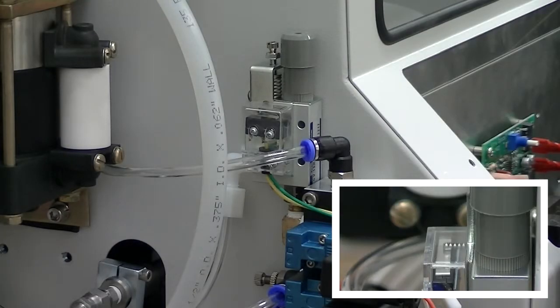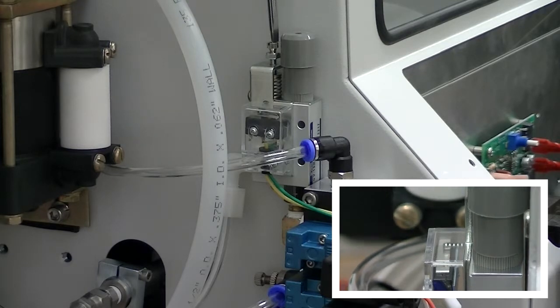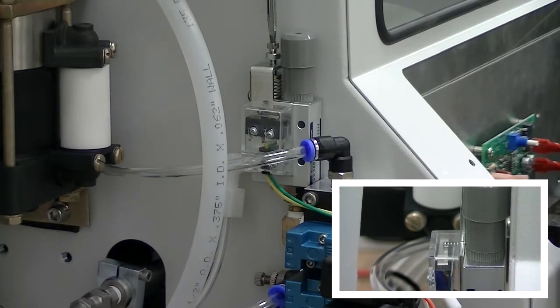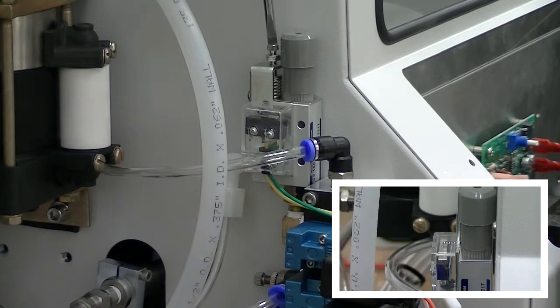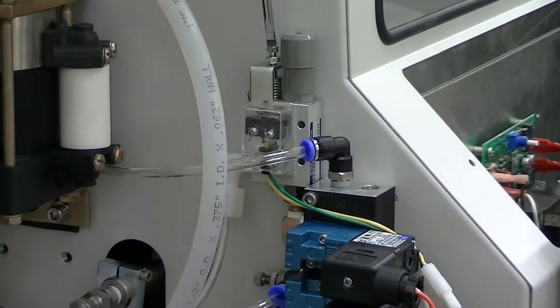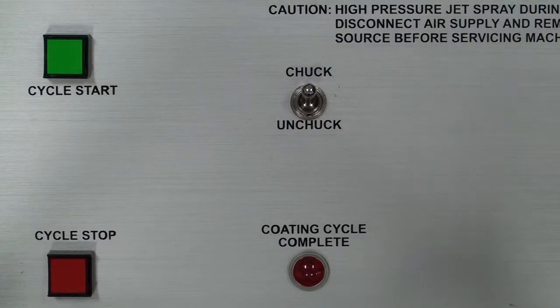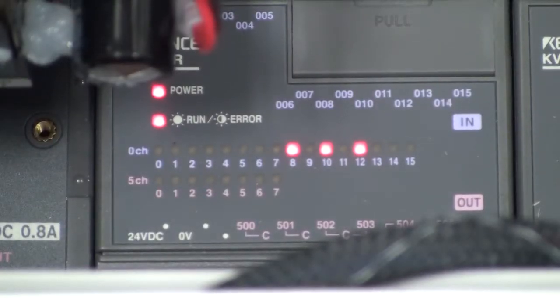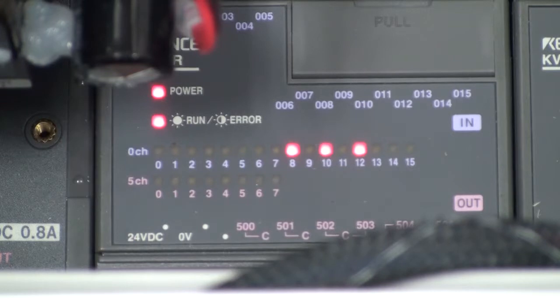If 7 light is still not on, use a flathead screwdriver on adjustment bolt on top of transducer to adjust signal contact. Unchuck the lens. With the lens unchucked, zero channel should only read 8, 10, and 12 again.